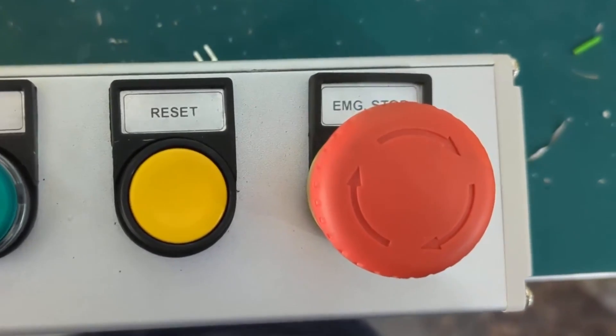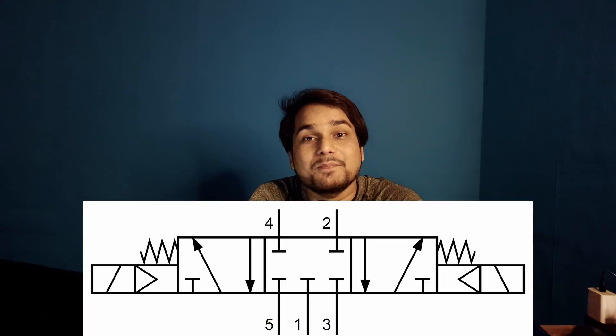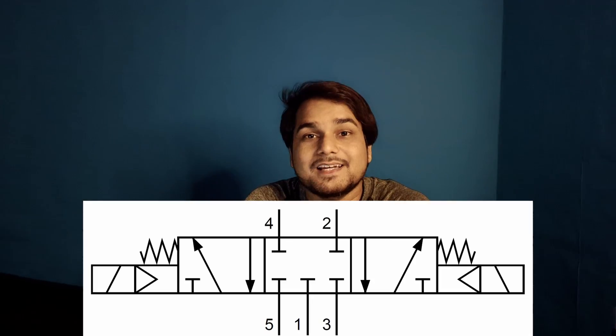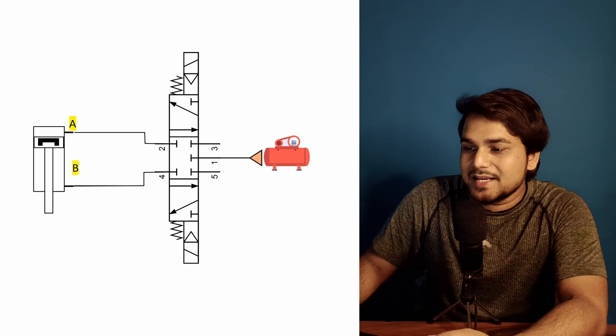What if you want to stop the pneumatic cylinder somewhere between the top and bottom — for an emergency or as a functional requirement? For that we cannot use the 5/2 directional control valve, because a 5/2 valve can only operate in two positions: position 1 the cylinder goes up, position 2 the cylinder goes down. We need a third position — a state where we can stop the cylinder — and that we can achieve with a 5/3 center closed valve.